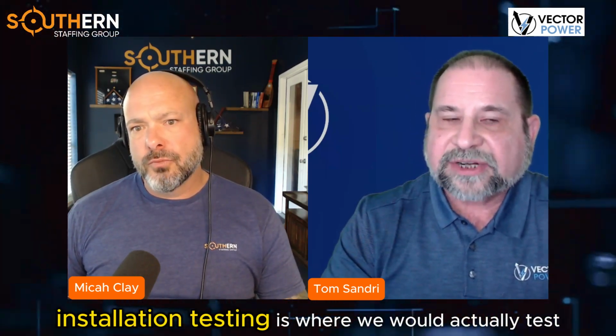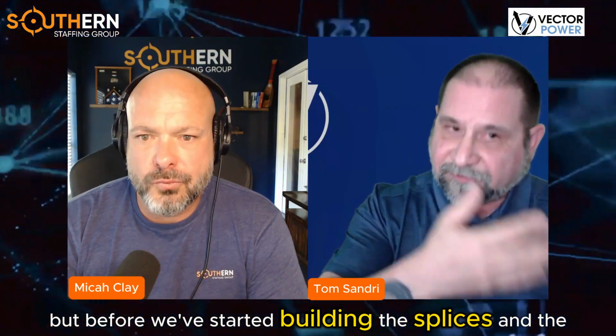testing as installation testing, acceptance testing, and maintenance testing. So installation testing is where we would actually test the raw cable before splices and terminations are put on. We can either test it on the drum, if both ends are available to us, where we can do our necessary cutbacks so we don't flash over at the flat cuts, or it could be after we've laid the cable into the trenches, but before we've started building the splices and the terminations. The goal of installation testing is to make sure that the factory sent you quality product. It didn't get damaged in shipment. It didn't get damaged in the initial installation. And we know now the cable is good before spending all the time and effort, because these splice kits and terminations are not cheap.